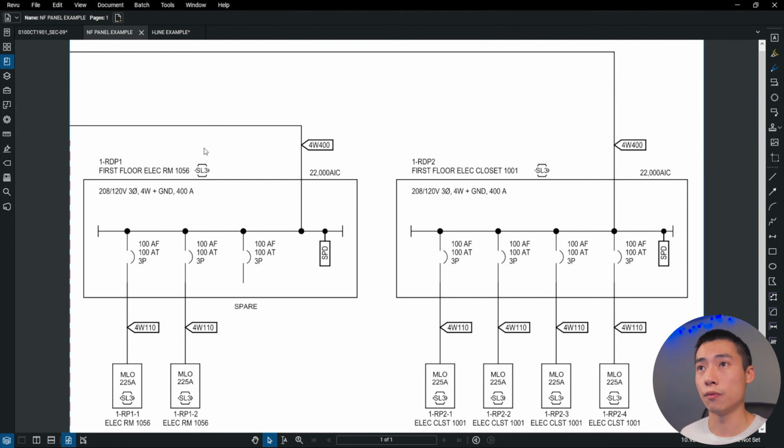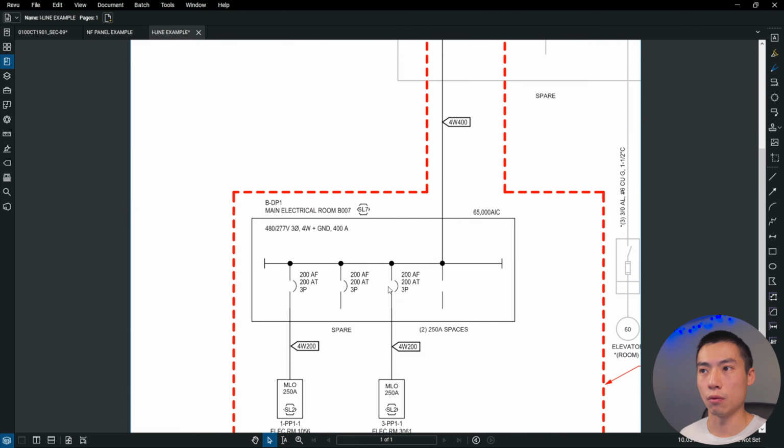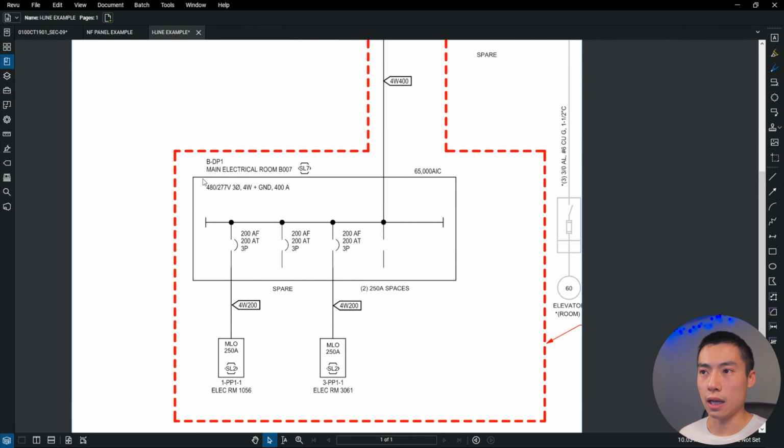What we have to do, here's the I-line. So the I-line, this is our fix to it. We drew it out now. We had, I think, 1, 2, 3, 4, 5, 6, 7 loads, and it didn't fit. So let me switch over to the Square D catalog where you can see how this is all spelled out.